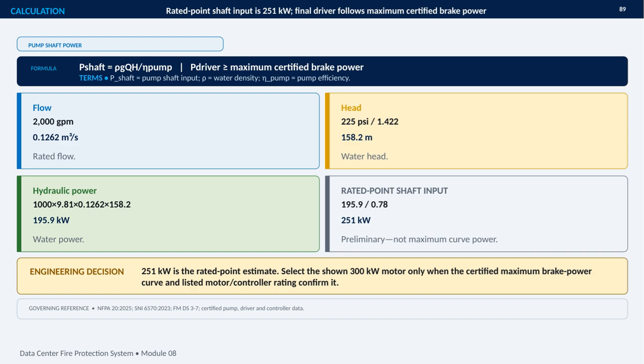The important qualification is that this is a preliminary estimate at one operating point, not necessarily the highest power the pump can demand across its certified curve. The final driver must follow the maximum certified brake power, not just the rated point calculation. Therefore, the 300 kilowatt motor should be selected only when the certified maximum brake power curve, along with the listed motor and controller ratings, confirms that choice. The governing references include NFPA 20, SNI 6570, FMDS 3-7, and the certified equipment data.